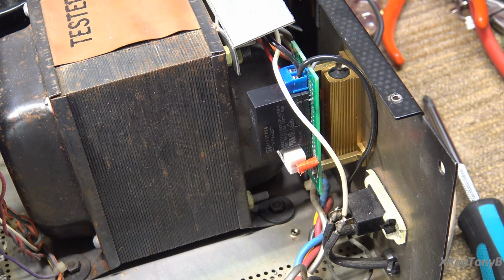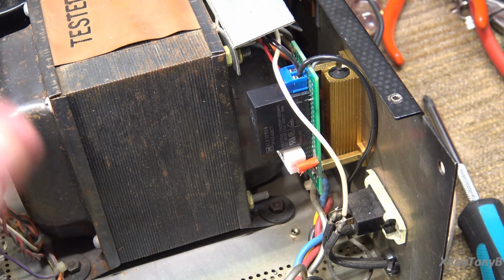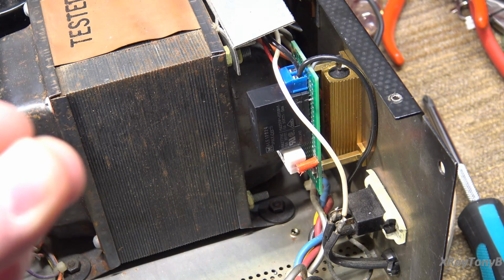Now I know some of you use them, and that's great if you like them. You're right, it will limit the inrush current, and you do not need the use of a relay. So just to reiterate, this is just my personal preference, I don't like them for that reason, because of the heat and all that other stuff. Also, even at their lowest temperature or lowest resistance, they still impose a resistance in series with the transformer.